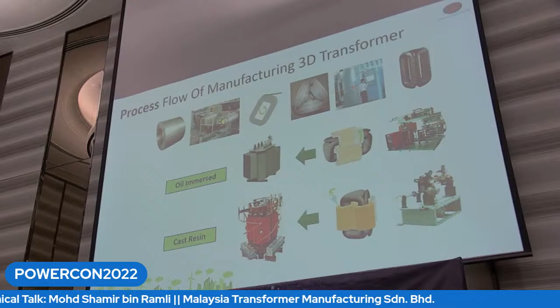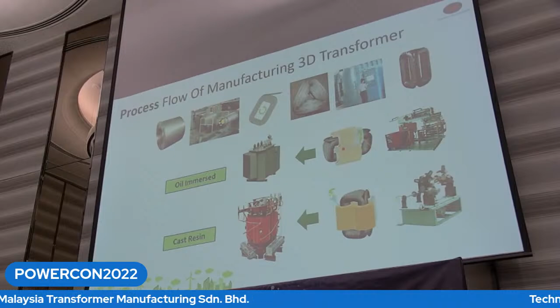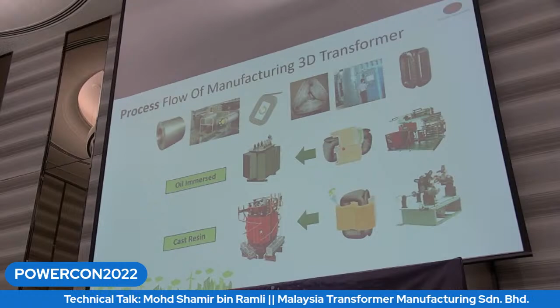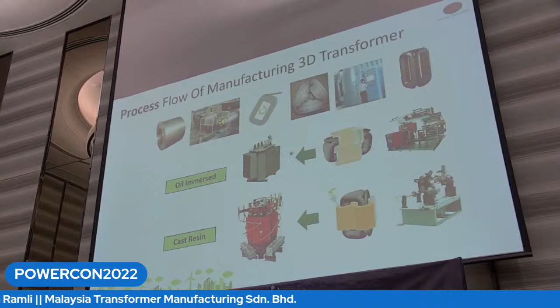This is the slitting coil, which is then slit here, and after that rolled together to form the 3D wound core. It's put into a vacuum impregnation chamber to give it strength. After that, it's taken out, and depending on whether it's for oil-immersed or cast resin, the copper is wound onto the 3D wound core. Unlike a conventional transformer, where the core and winding are built separately and then assembled, here you wind the copper directly on top of the 3D wound core. Once the copper is wound onto the core, you can tank it inside the transformer tank and it's ready for testing. This process is similarly done for the cast resin transformer as well.